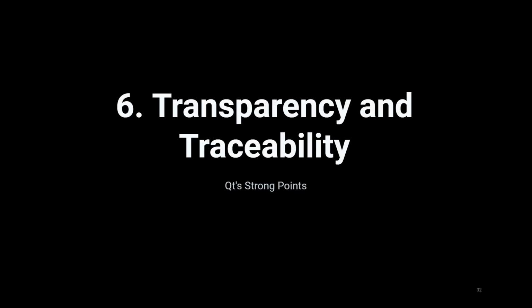If you are familiar with the 62304 for medical projects, you know that no one can tell you exactly what you should do and how to do it in terms of medical device, medical software documentation. It rather tells you to describe your processes and explain yourself how you are mitigating risks in your project. This includes verifying third-party software, like the dependencies that you used. Yeah, and here one aspect cannot be ignored.